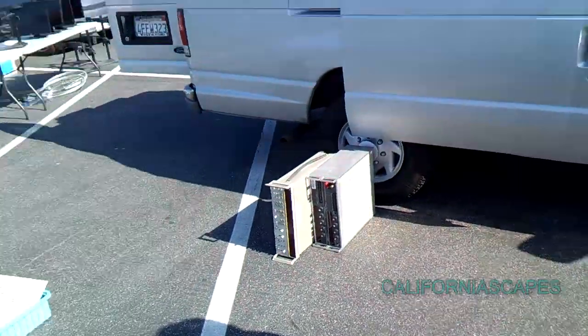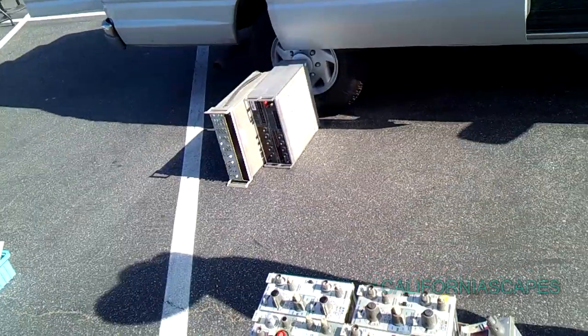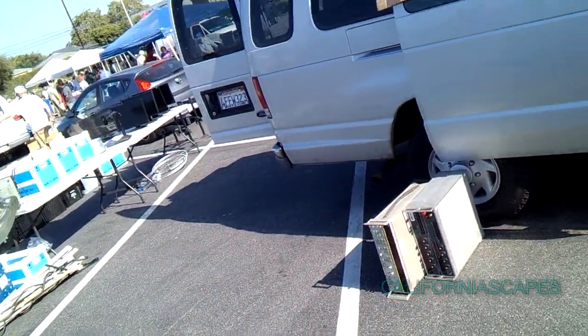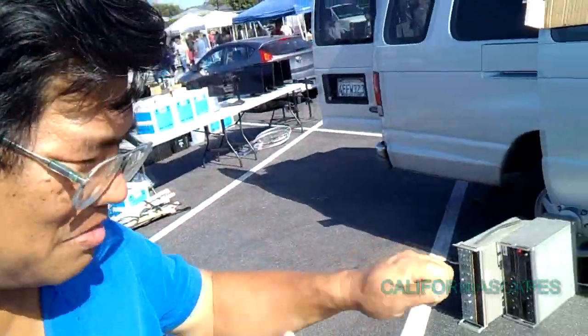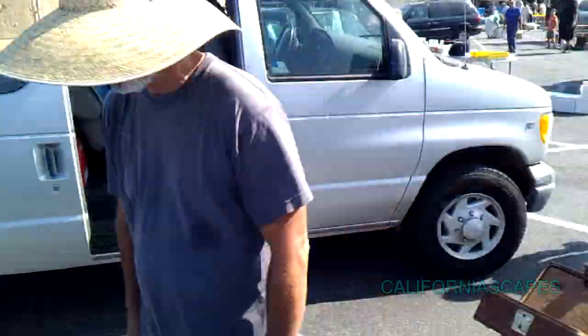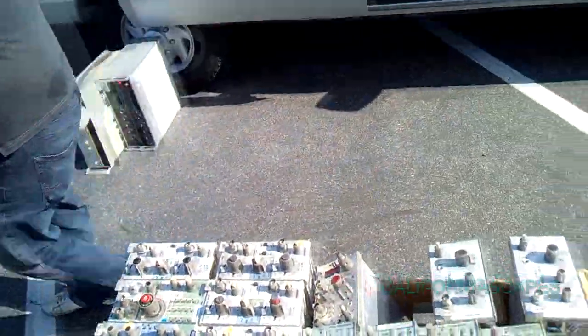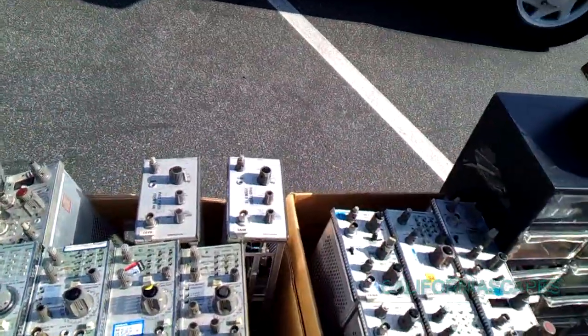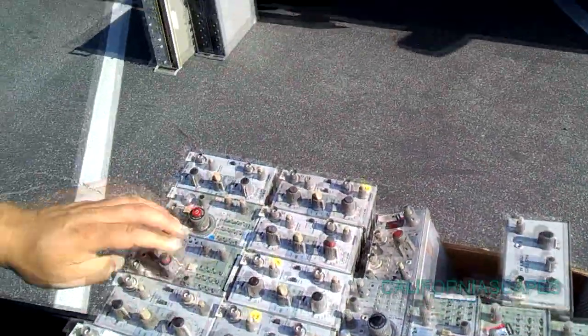Lucky, the time bases are difficult to calibrate. You have to have the scope to do that. And of course, working at Tektronix, I had the extenders. They don't make them anymore. They want you to replace them every 5 years. Oh, I understand. Charles has the scope pulled out. Right, yeah. Got it, put it back in there. Does it work now? Yeah, and of course, all the original tested components to fix them. See, what wears out on these are these push buttons, these things right here. They're troublesome.